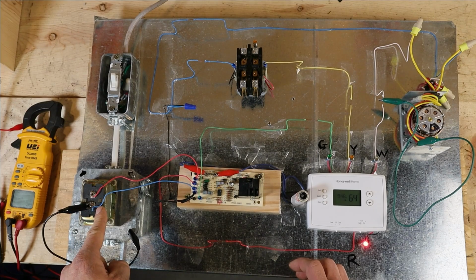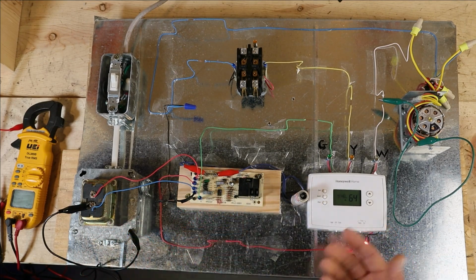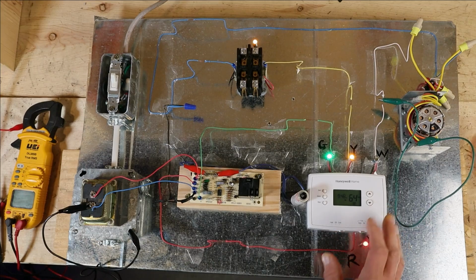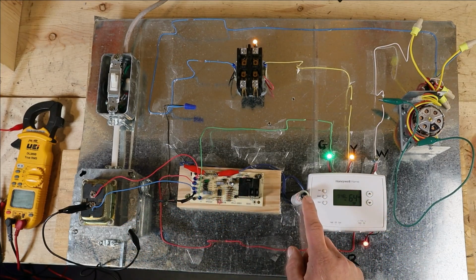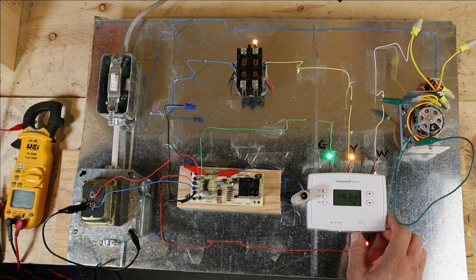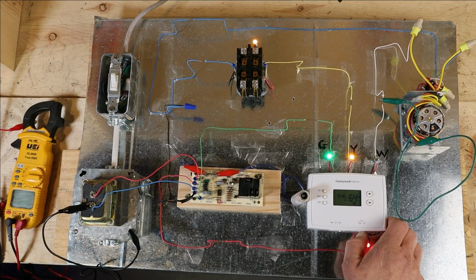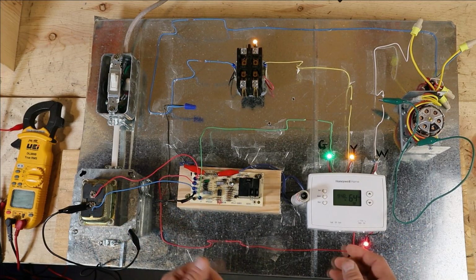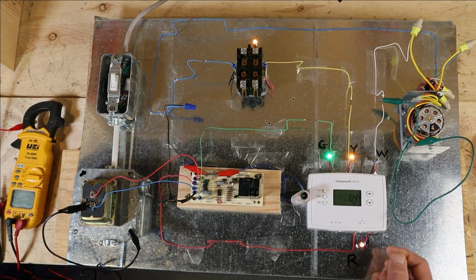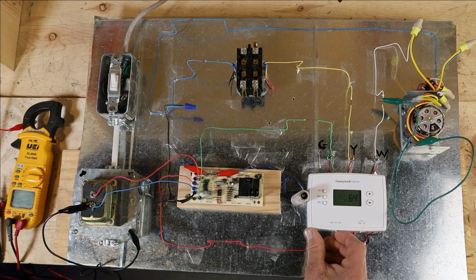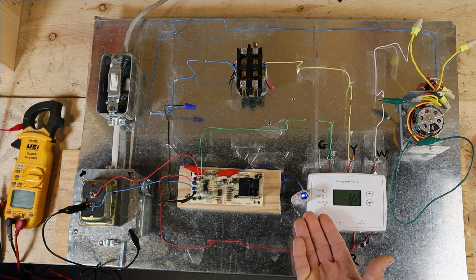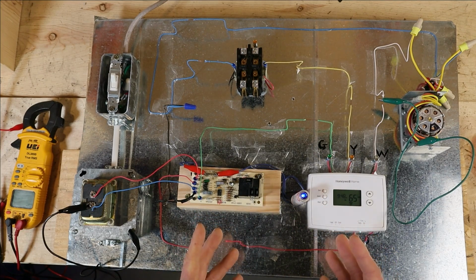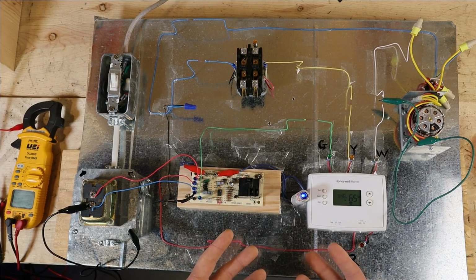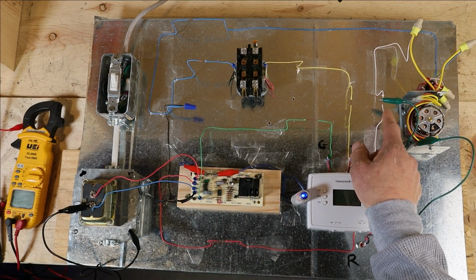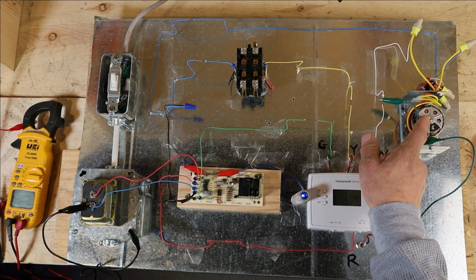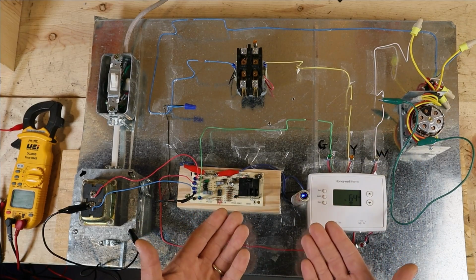And as we indicated before, this metal is grounded, and with a grounded secondary we now have a path going back to common. So what I do is put it in cooling mode, and you can see everything works. We have no short being indicated. We can turn our fan to the on position. Everything's still fine. Turn our fan back off. But once we put it into heating mode, we now have our short. Now on a grounded secondary, this doesn't really tell us whether the short is occurring with a bare wire touching metal or the actual failure of the component itself to provide any resistance.